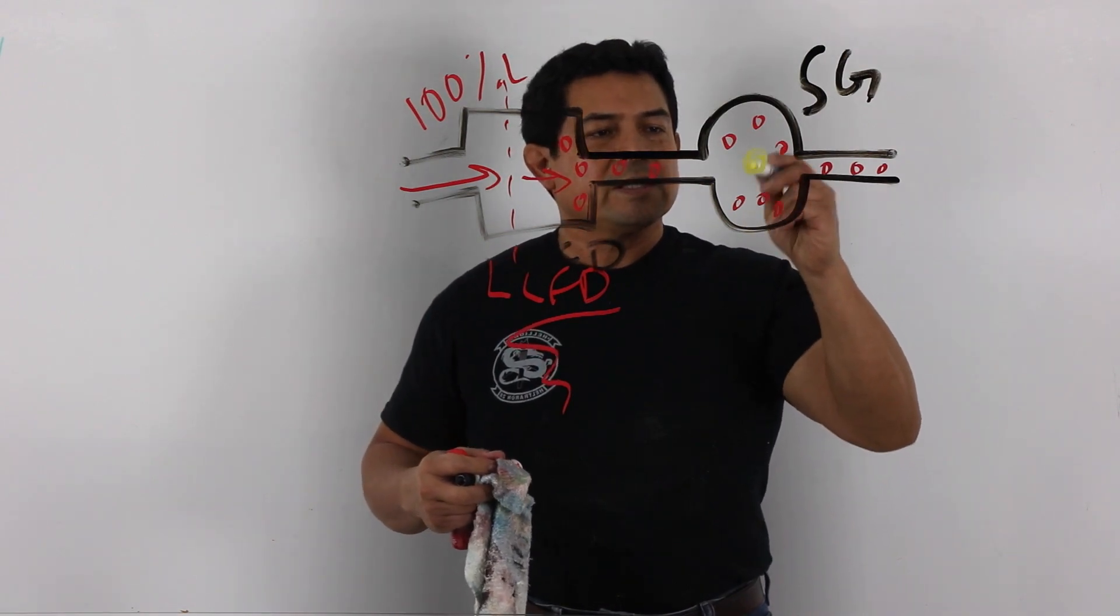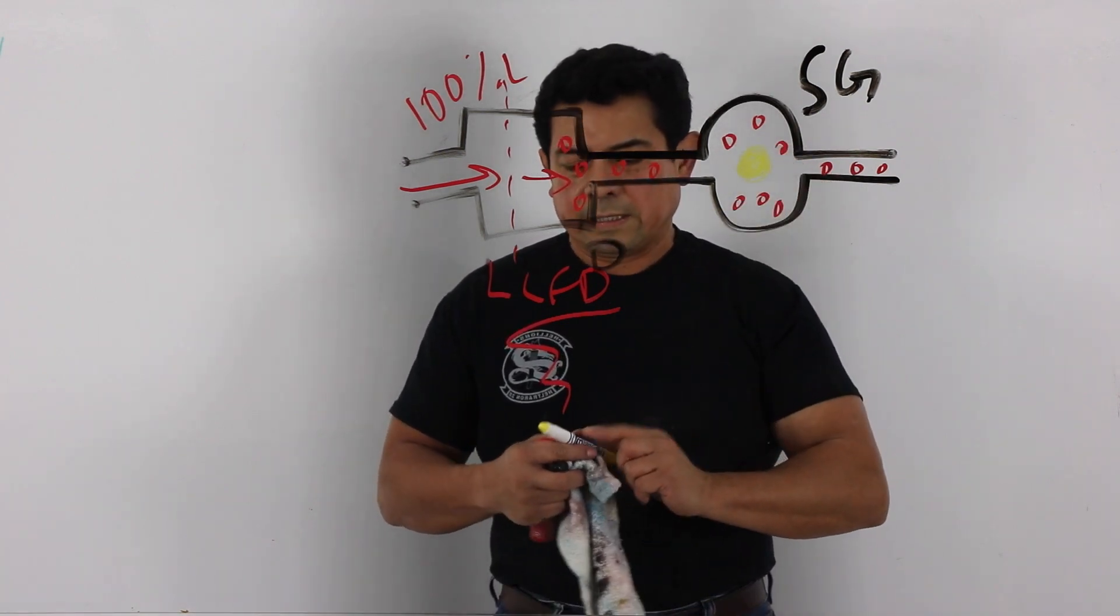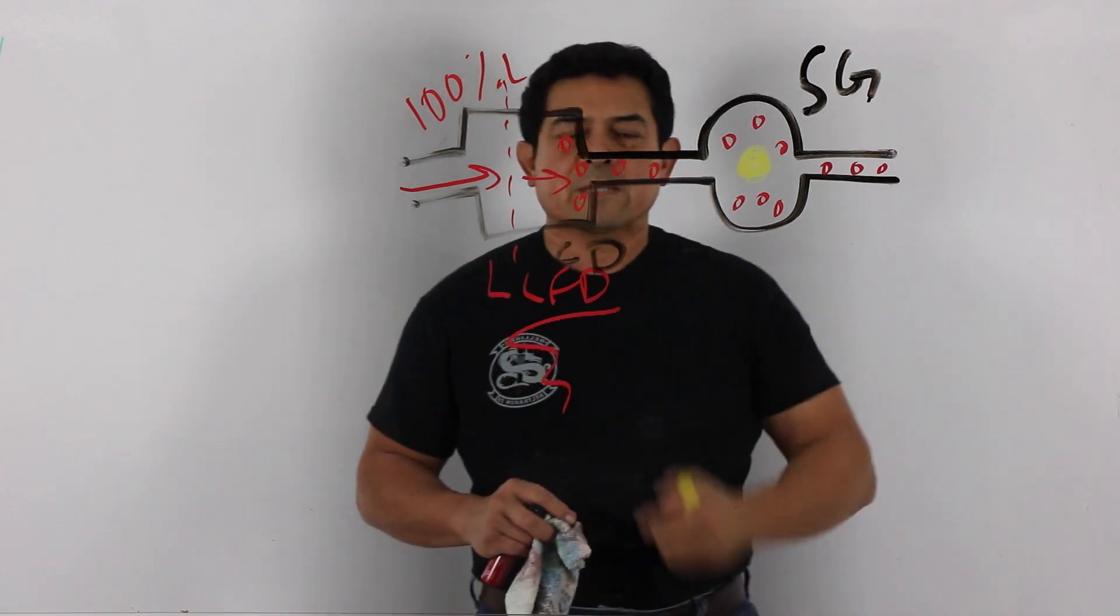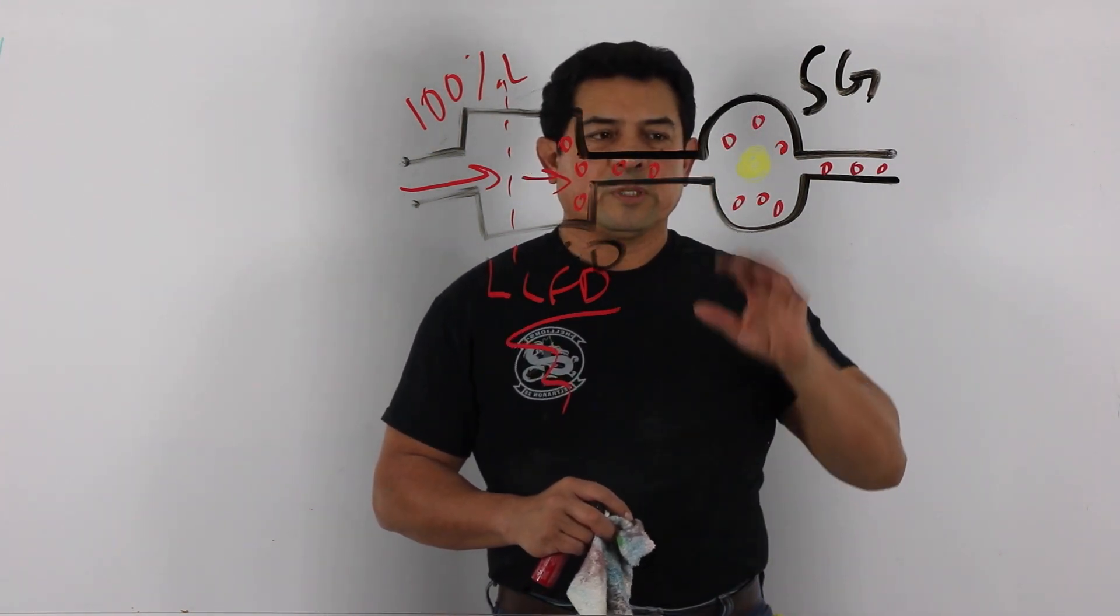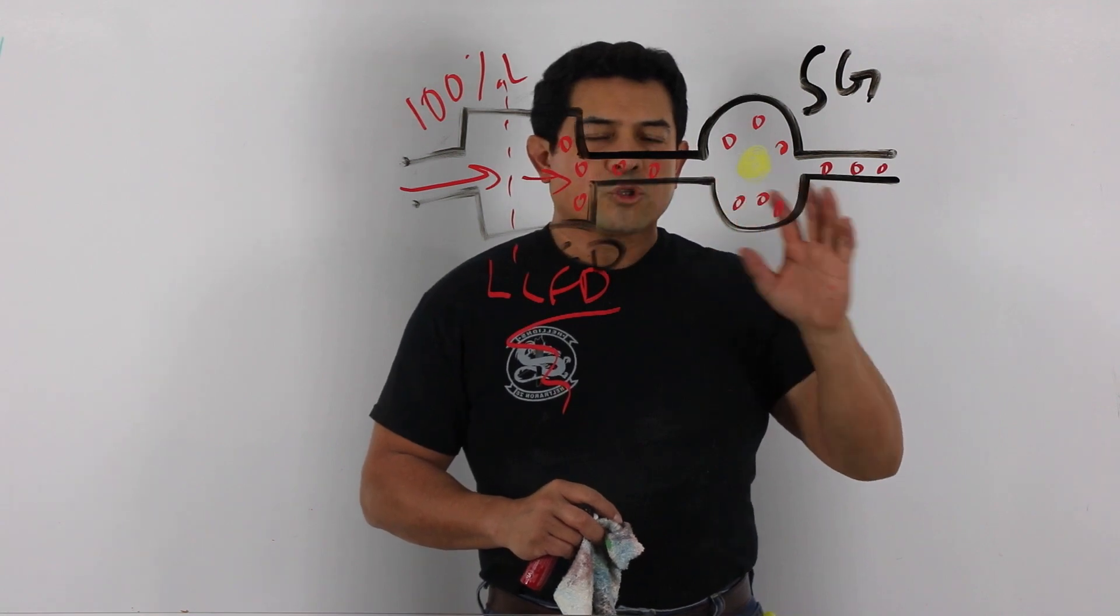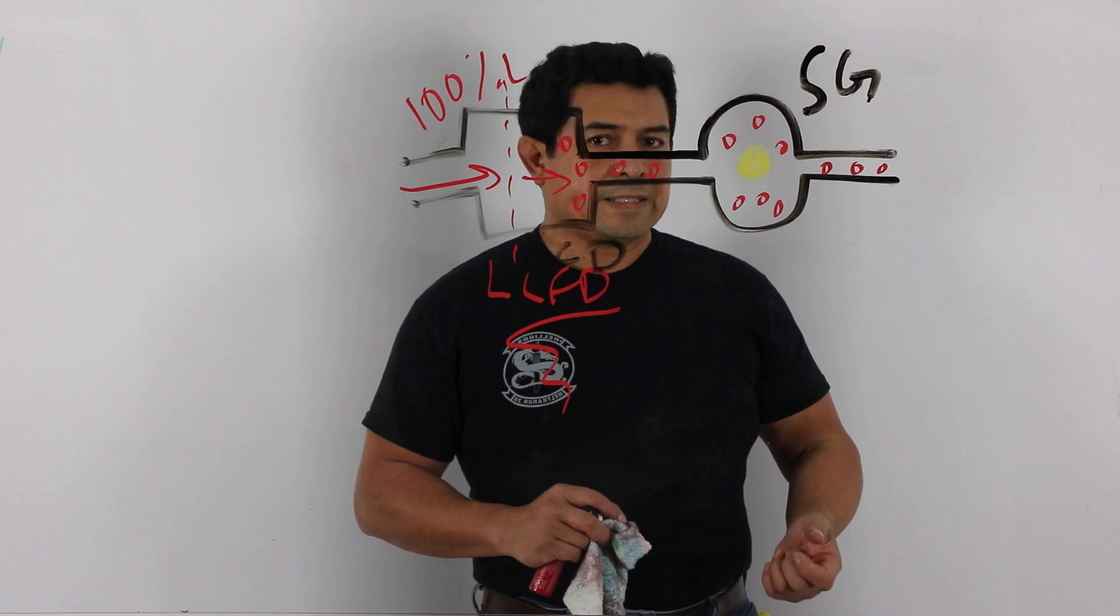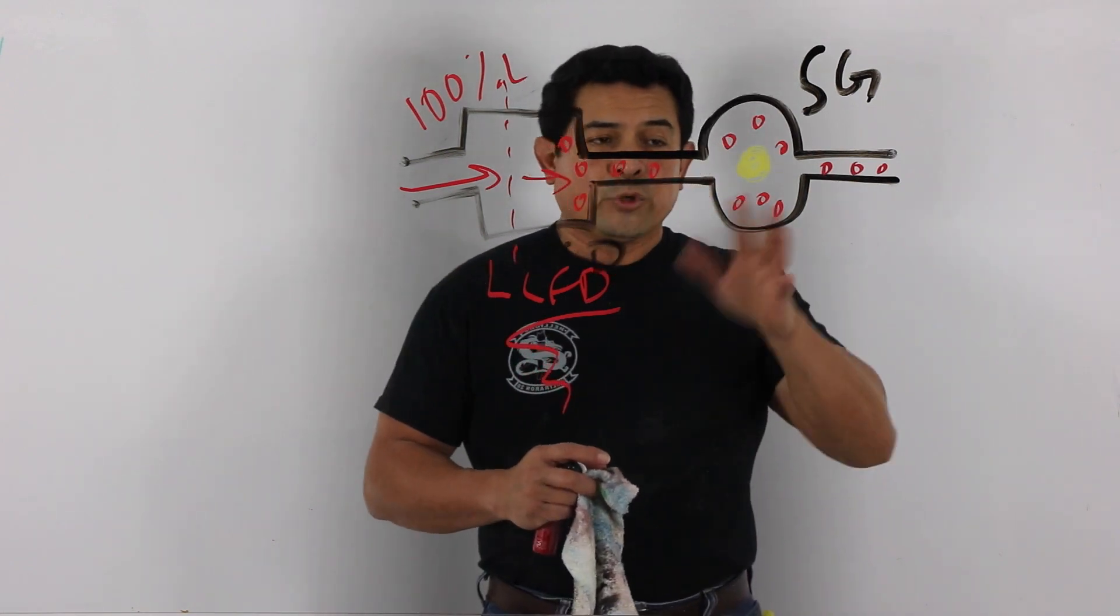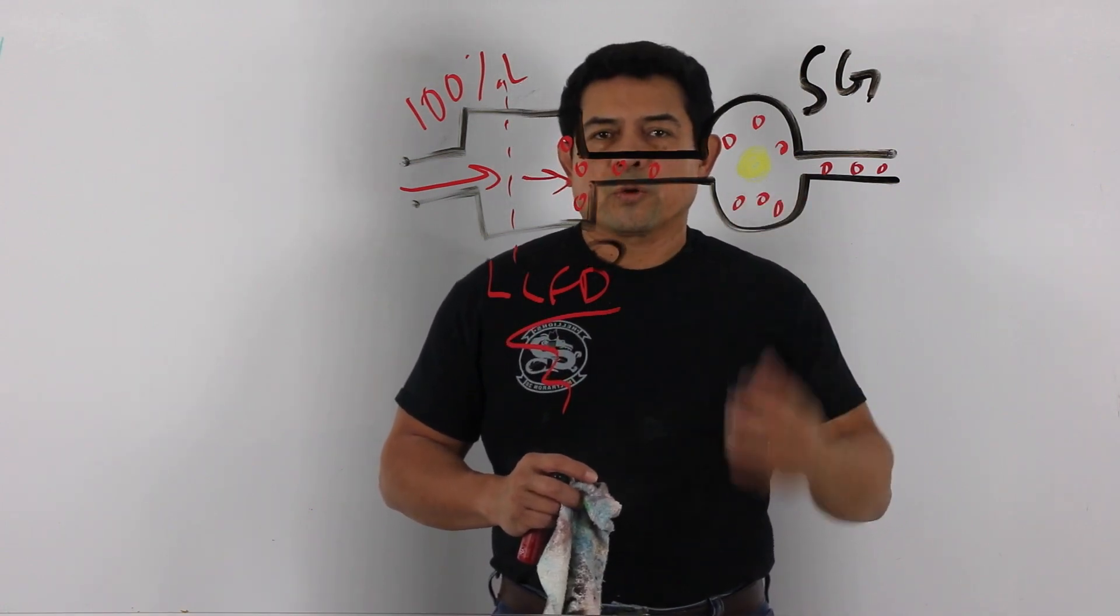Sometimes you're going to see that it is yellow. Well, if this has turned yellow, that tells us that there's moisture in the system. That means that now the system has been contaminated with moisture and that's going to create a problem because what does moisture do in a refrigeration system? It creates acid. The moisture creates acid in a system, so we don't want that. Anytime we see this, we know that there's moisture. So what are we going to do? How are we going to get rid of this moisture?